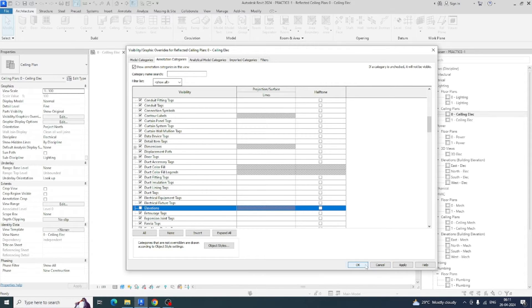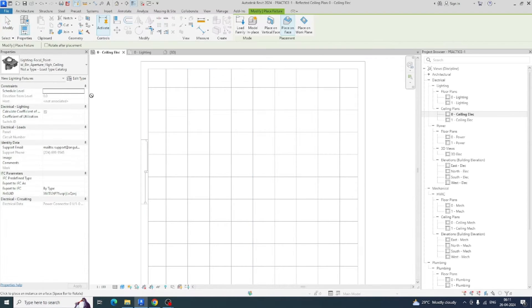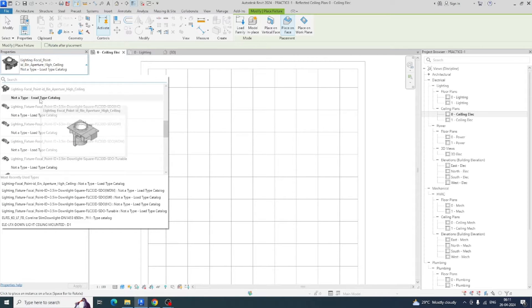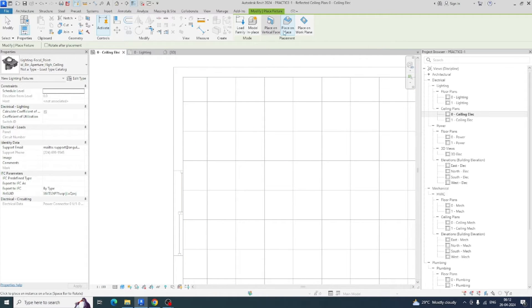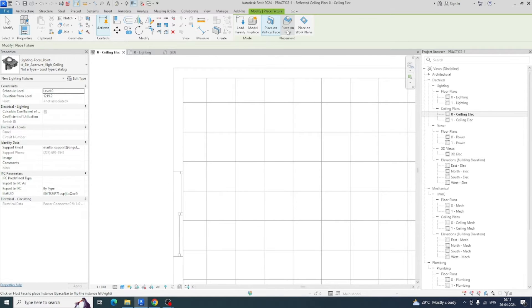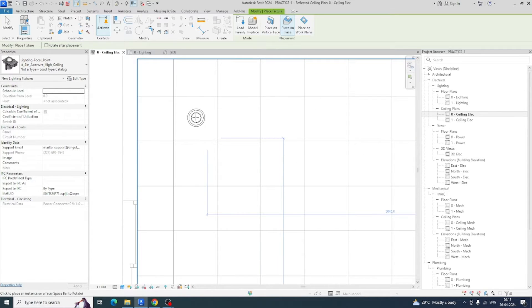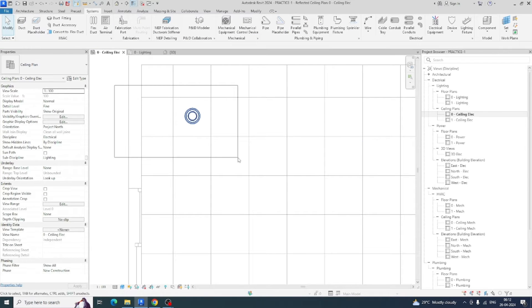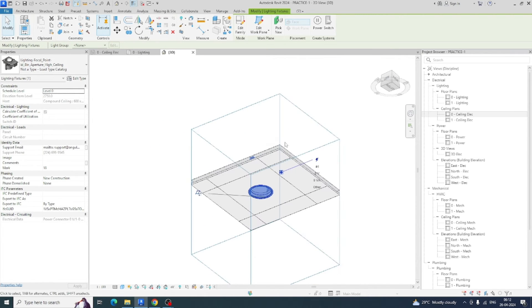I'm going to VV and adjusting the elevations, then we need to fix lighting symbols through this ceiling. Go to System, then Lighting — there are a lot of lighting fixture families. I'm choosing one and there are options like vertical and place on face. I'm using place on face and placing one light in the center of the ceiling. Check in the 3D view — you can see it was fixed in the ceiling.